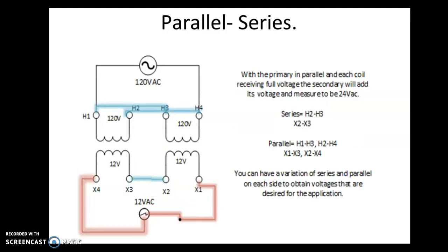From the same example of parallel parallel to a parallel series connection, we see full voltage applied to the primary coils at 120 volts apiece. By inducing 12 volts per coil on the secondary side and putting that in a series connection instead of a parallel, this voltage will actually add and that should be 24 volts AC.